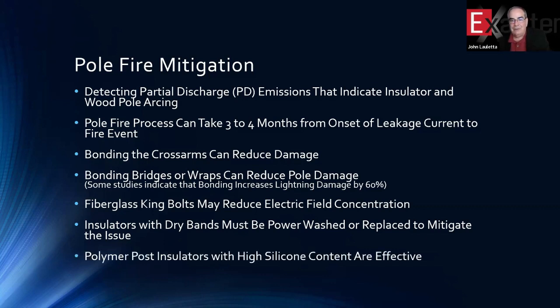Polymer insulators are better, but they themselves over the decades of use have gotten better. So the older polymer insulators may contribute to this problem more than newer ones. So again, you don't have to worry about it if you detect the problem by listening for these partial discharge signatures, because they'll be there regardless of the insulating materials that are used.